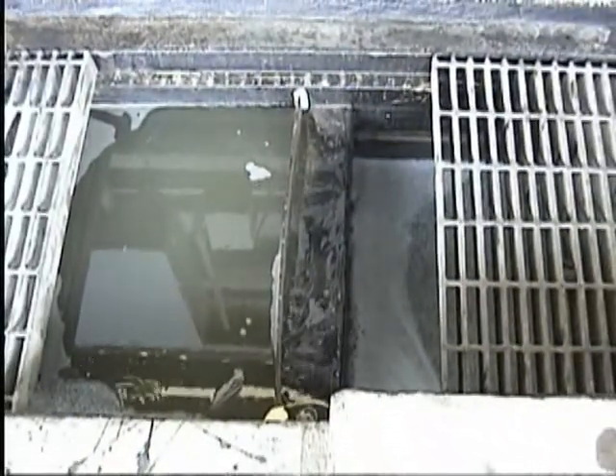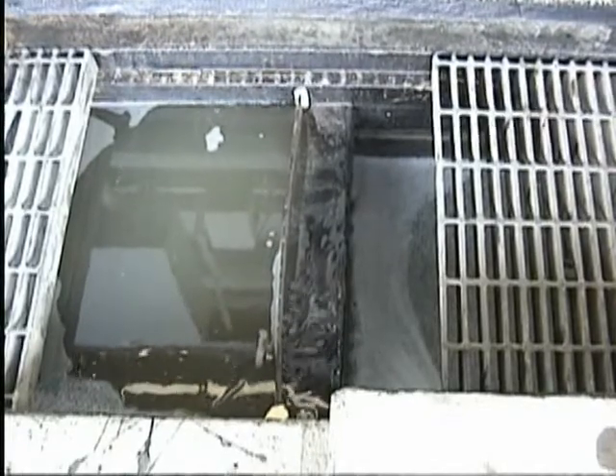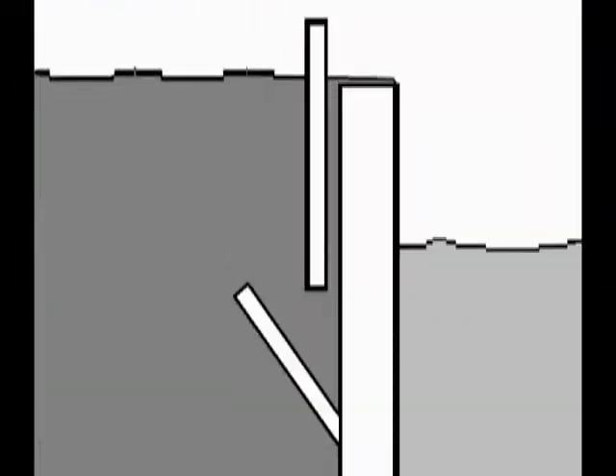As wastewater is added to the east wash sump, the wastewater passes under the skimmer plate and over the sump separation barrier and into the center accumulation sump for further processing. The skimmer plate keeps a large portion of the floating contaminants out of the center accumulation sump by allowing only wastewater from 6 inches below the surface to pass.